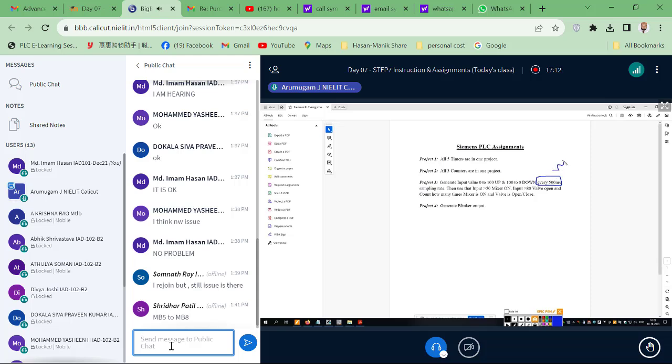That means if you go from 0 to 100, how much time is taken? Already I told you, right? With an update rate of 500 millisecond, it takes 50 seconds, because in 1 second there are 2 increments.